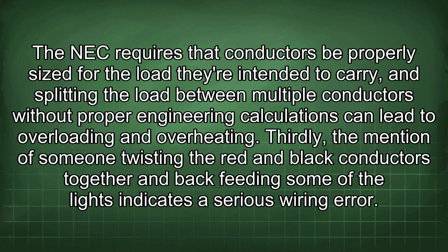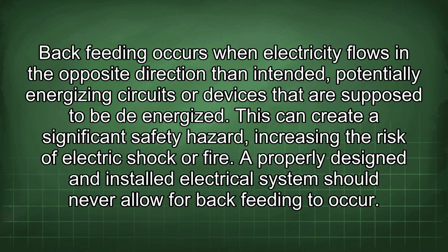Thirdly, the mention of someone twisting the red and black conductors together and backfeeding some of the lights indicates a serious wiring error. Backfeeding occurs when electricity flows in the opposite direction than intended, potentially energizing circuits or devices that are supposed to be de-energized. This can create a significant safety hazard, increasing the risk of electric shock or fire. A properly designed and installed electrical system should never allow for backfeeding to occur.